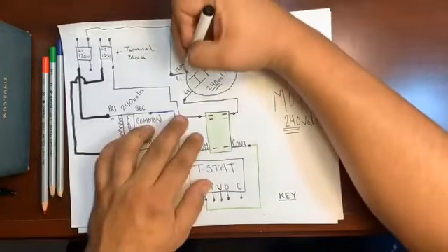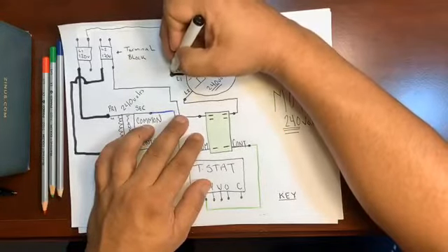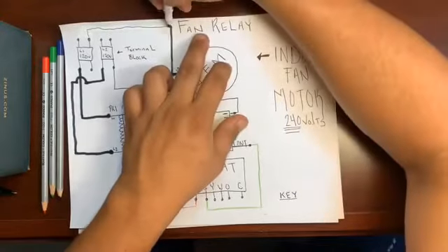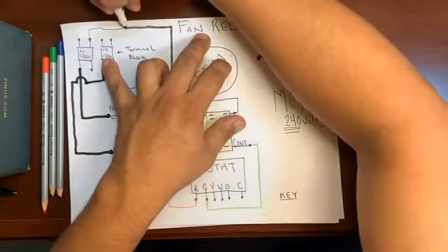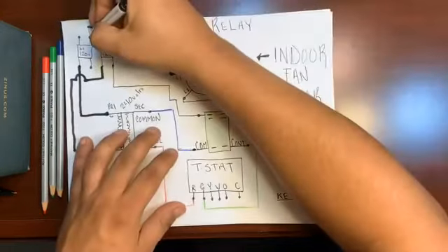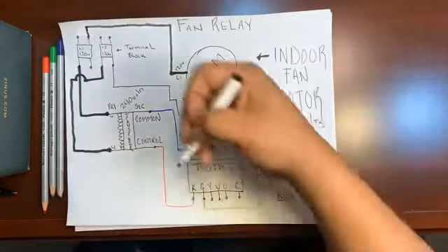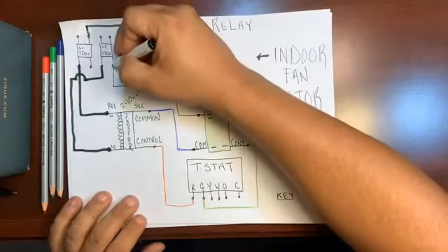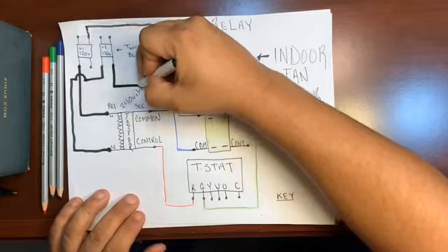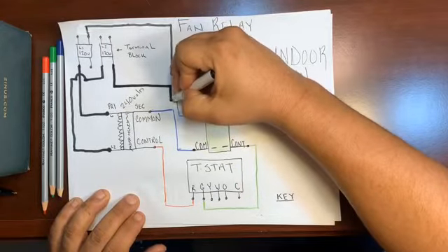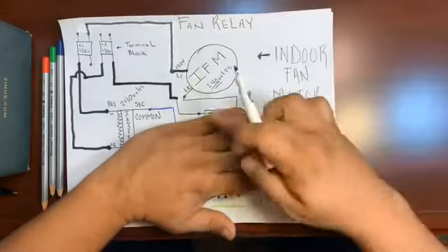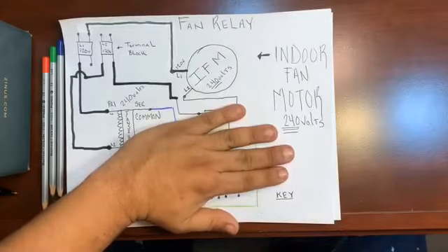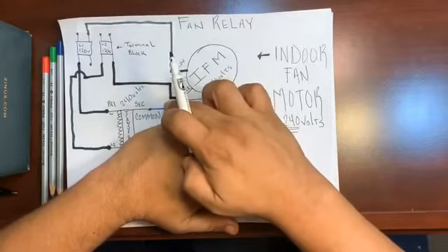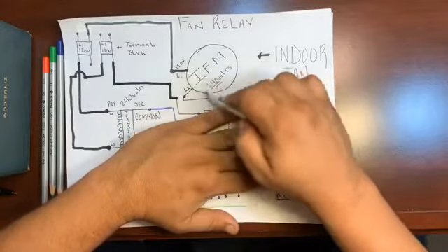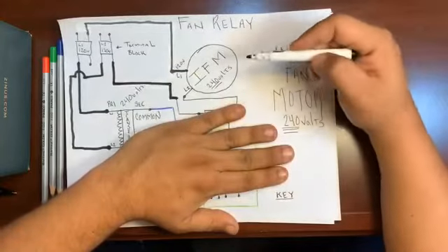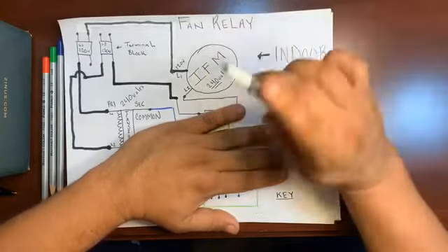We're gonna go ahead and complete our common, 120 volts. Bring it up, over, and all the way back down. And that just leaves our L2 control that needs to come down, come over, down again, over. Look at how close this wire is to that fan motor relay. How easy it is to want to put this L2 directly to L2, but if you do that, this fan motor would have its consistent 240 volts. It would turn on. It would never turn off. The thermostat would have no control.